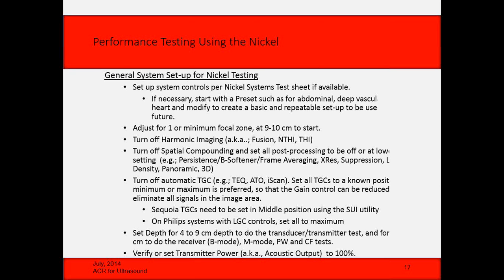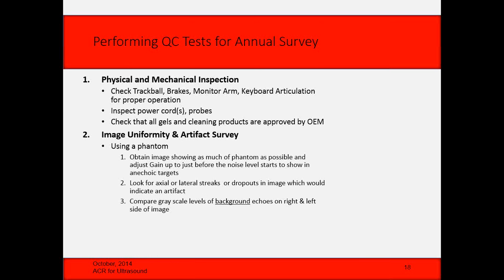And then, of course, you want to, as I mentioned earlier, compare the grayscale levels of the background echoes on the right and left side. This is the way I do it. As I turn the gain up until there's noise, you know that noise is uniform in the system, right? Because it's just the general system noise. And then I compare the grayscale levels of the noise on the left and the right, and that's how I do image uniformity.